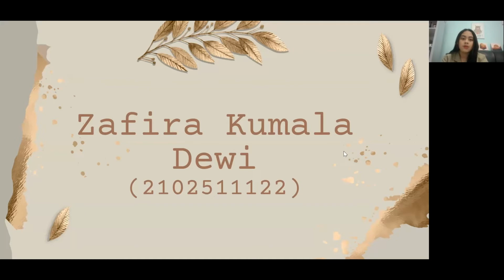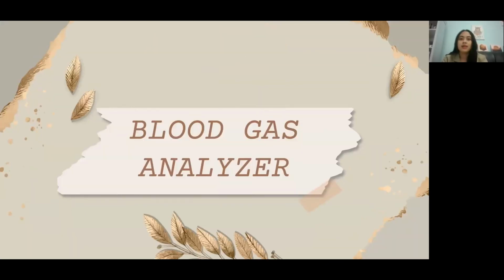Now I will continue the explanation about blood gas analyzer. Blood gas analyzer is one of the most important tests used for diagnosing and managing patients, especially patients with pulmonary disease. This device is used to analyze the concentration of oxygen, carbon dioxide, and acidity or pH level in the whole blood sample. Blood gas analyzer has a handheld device with an LCD display, a keyboard to input information, and a slot to insert a small tube or test strip. It also has an onboard printer to report the result.